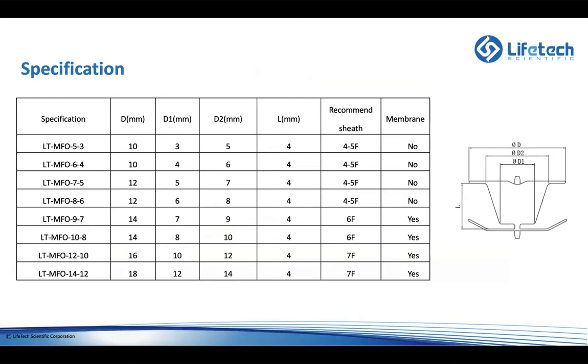So this is just some of the measurements of the device, easily found from the company. But like most devices, there's the larger waist, for the smallest device being the 5 millimeter, the smaller waist being the 3, hence how they name it a 5-3. And then the retention discs have an extra 5 millimeters on top. And that just allows it to be able to capture in the myocardium. And obviously it's good to know how much extra, because you need to plan that when you're looking at whether you have a small rim under the aortic valve, and where your device is going to be placed in the septum.